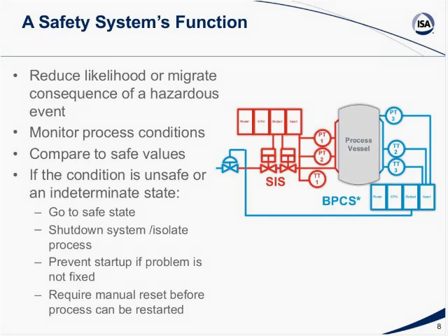Okay, first of all, I'm going to talk a little bit about the function of the safety system. It's to reduce likelihood or mitigate consequences in the event that you have an issue with your system. For example, if something should go wrong, it should address and manage that problem within that condition. It monitors and controls the process. It compares these values to safe values. If the condition is unsafe, you may go to an intermediate state, or systems go to a safe state. And I want to emphasize this point that going to a safe state is very important rather than going to a shutdown. If possible, it's good to keep systems running because it seems that most incidents occur on restart after shutdown. Shutdown systems isolate the process, prevent startup if a problem is not fixed, and require manual reset before a process can be restarted. In other words, make sure the system is corrected before you try and start again.